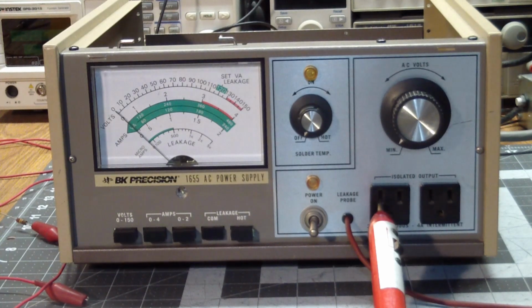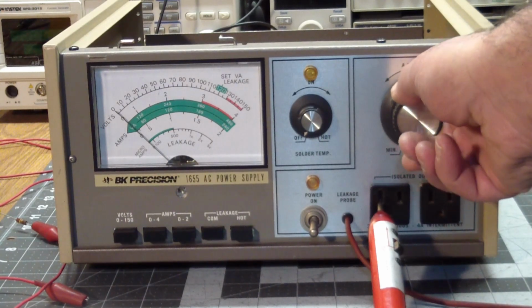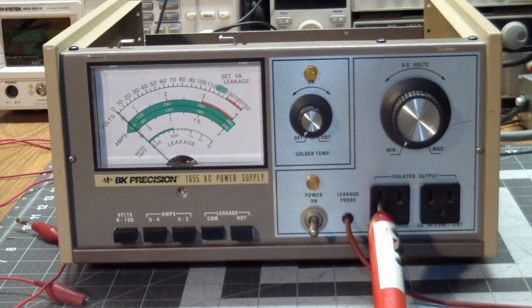Well, the calibration I tried, as outlined in the manual, was a bit vague and didn't work. I didn't get any meter deflection. However, when we get to the performance test, it passes. So I'm going to assume I did something wrong or my meter blew the current fuse or whatever. But the performance test basically says reduce voltage to a minimum and connect the leakage probe to the hot side of the isolated output.